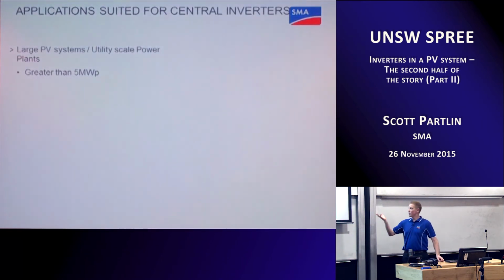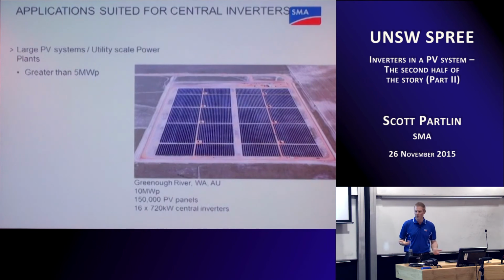So obviously that size point is probably around the 5 megawatts peak. Once you get above that, the costs and the benefits tip in favour of central inverter solutions. So this is an example of a utility, well, a large PV system in Australia. It's over in Greenough River in WA. It's 10 megawatts. It's got 150,000 panels and it's got 16 central inverters.